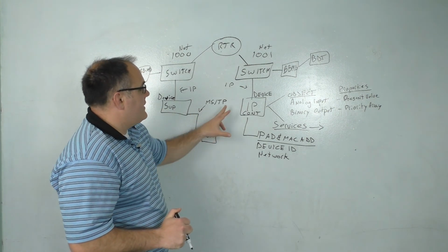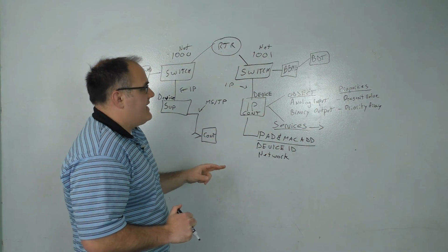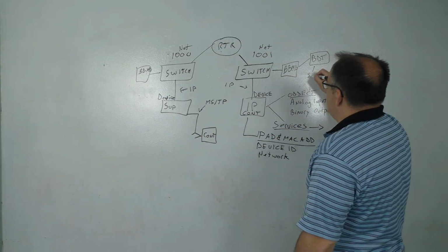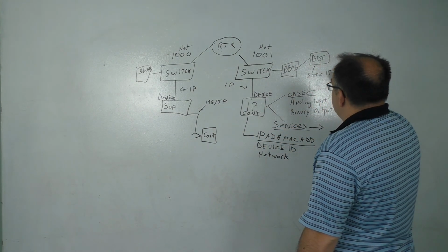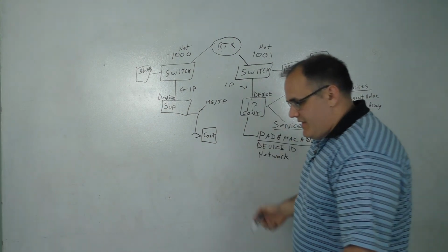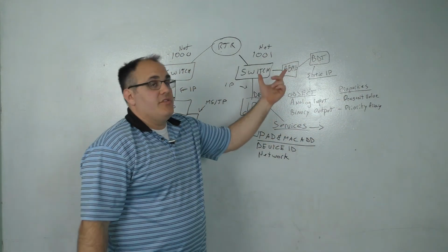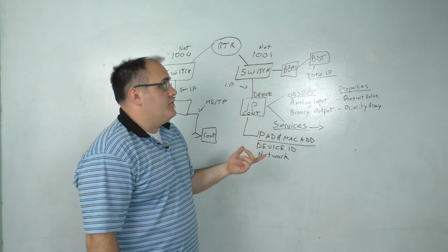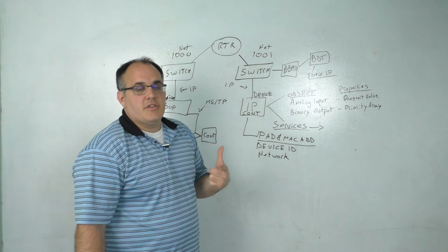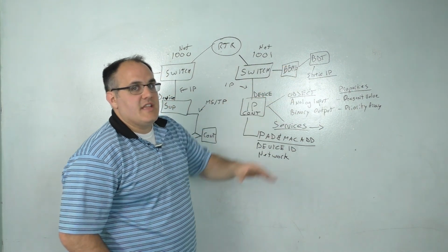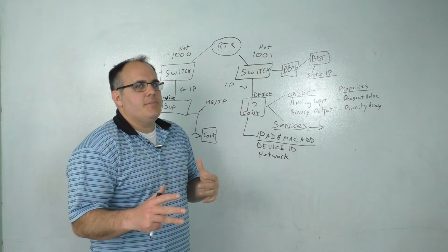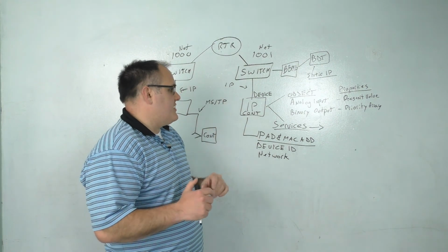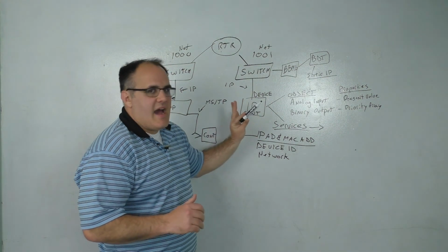As we were talking, one more thing popped into my mind: with BDTs, these need to be ideally static IP addresses. The reason is if these IP addresses are changing, and you're using manual BDTs, meaning someone's manually putting in those IP addresses, which some manufacturers do, then using dynamic host configuration protocol can actually cause some issues. That wasn't in the notes of what I was going to cover in this episode, but it's something I've seen a lot in the past that's caused a lot of issues, so I wanted to make sure I pointed it out. Okay, so we've got IP.